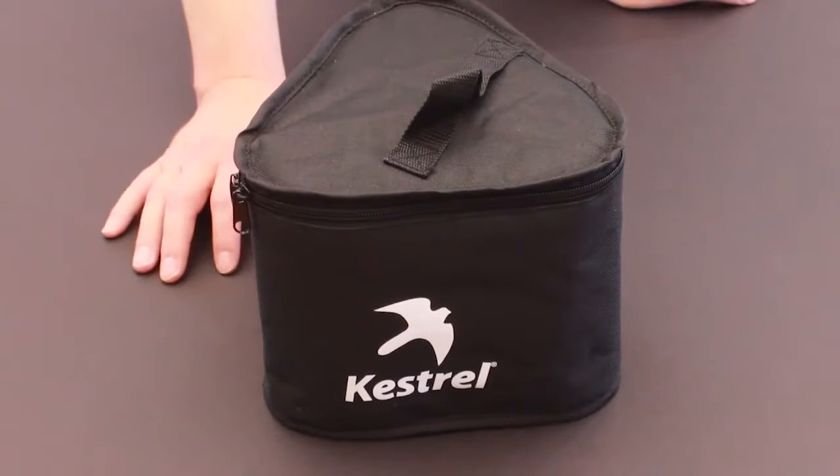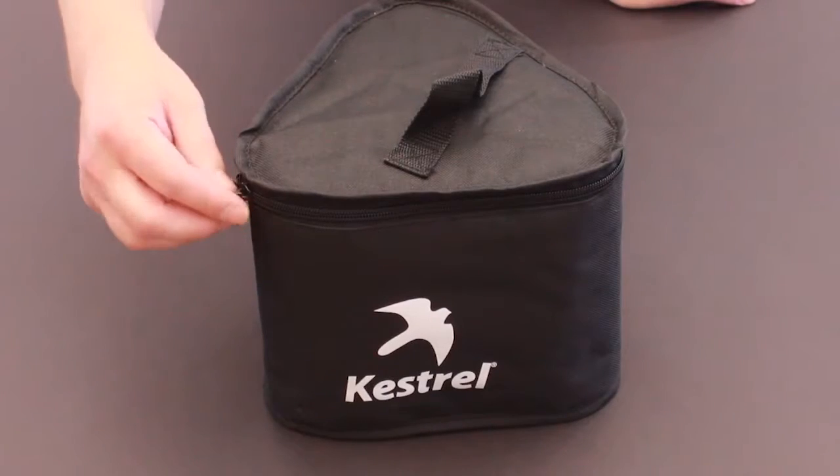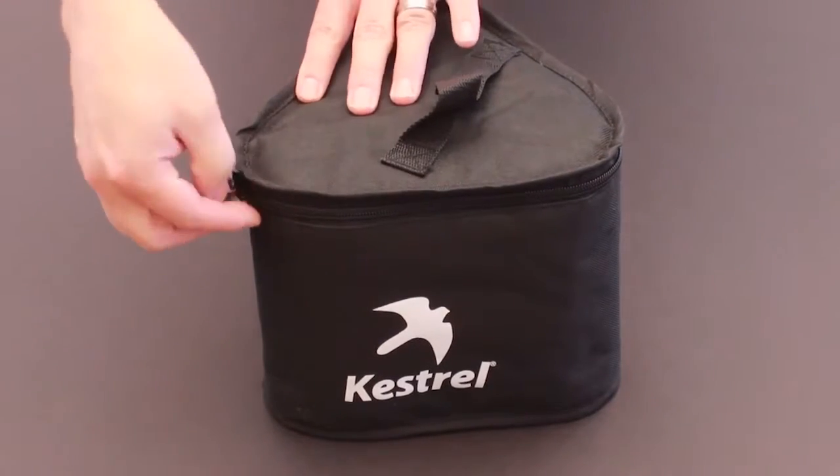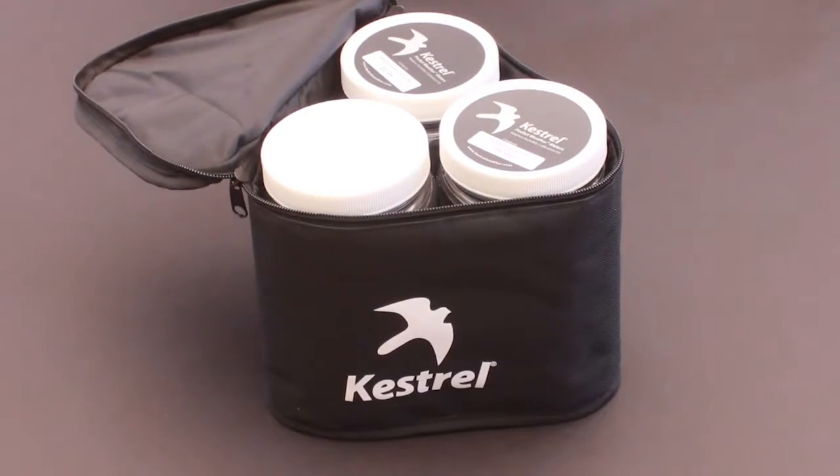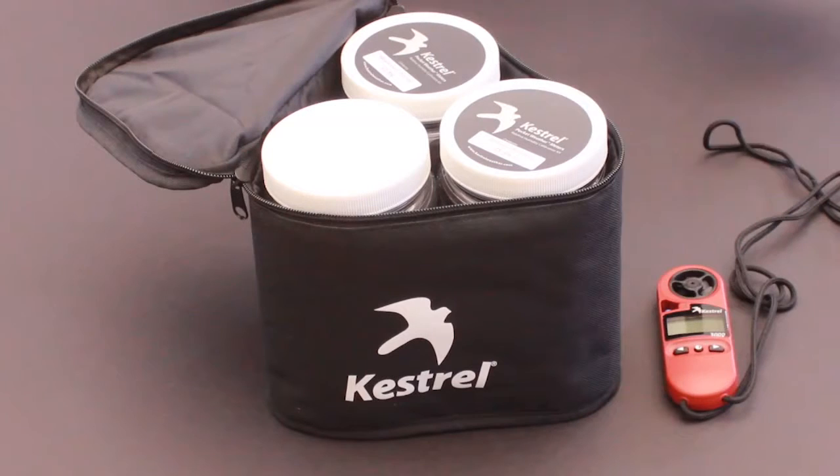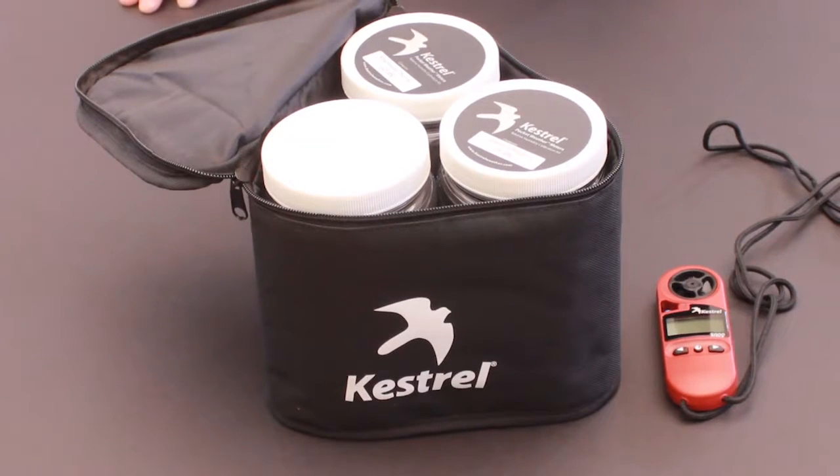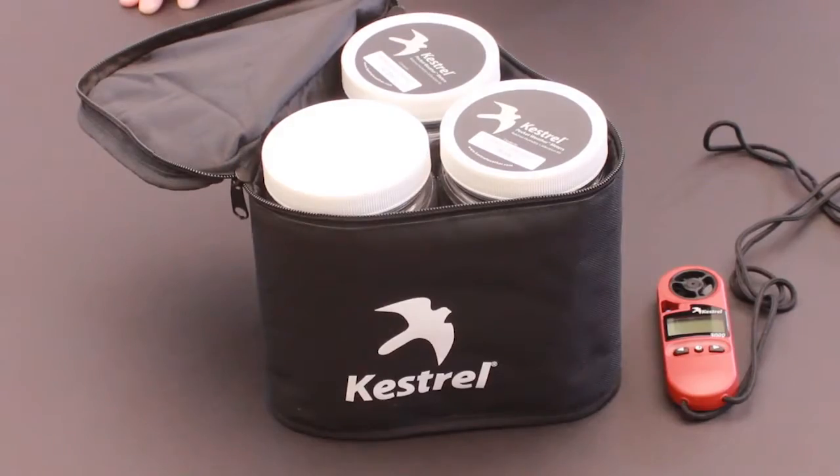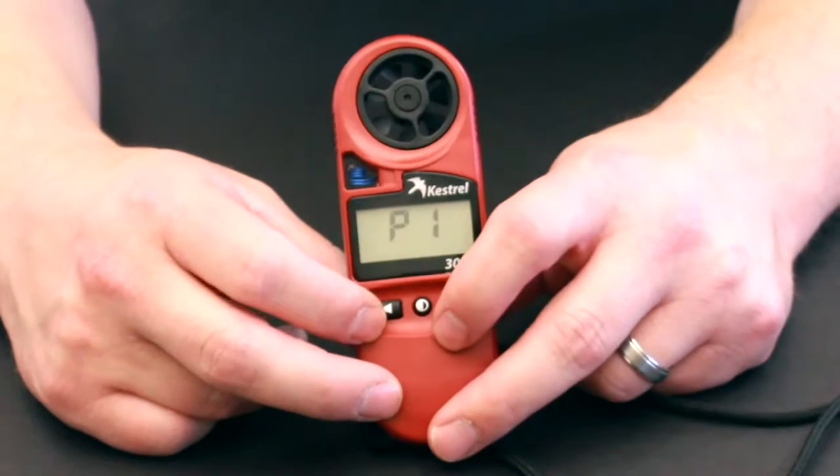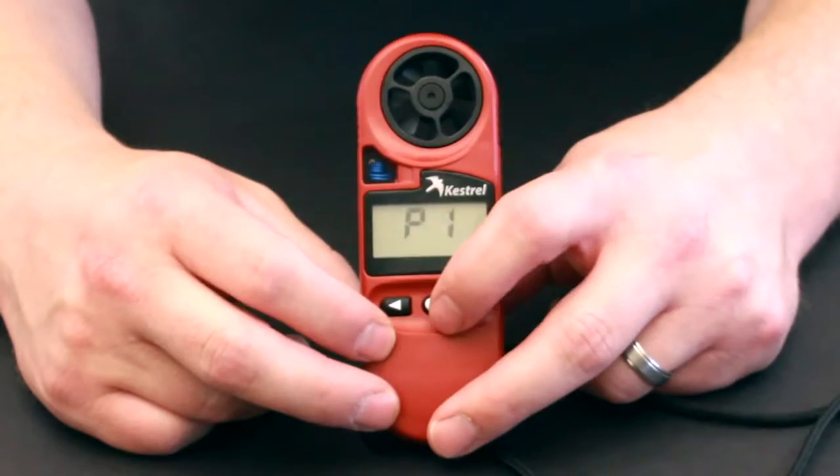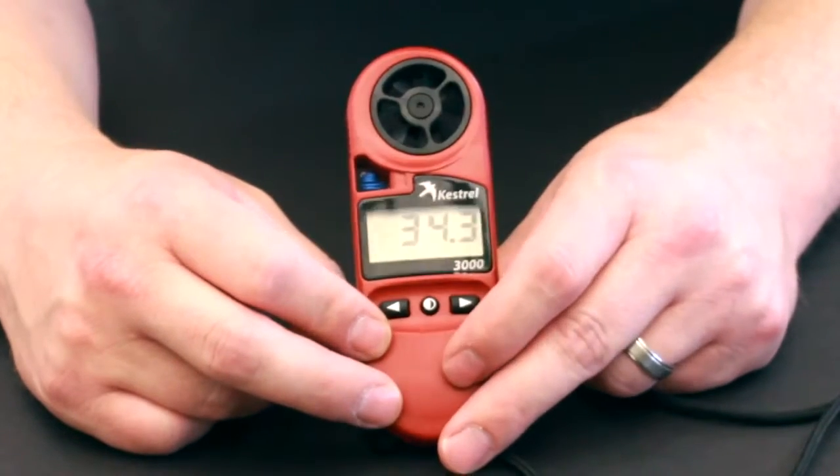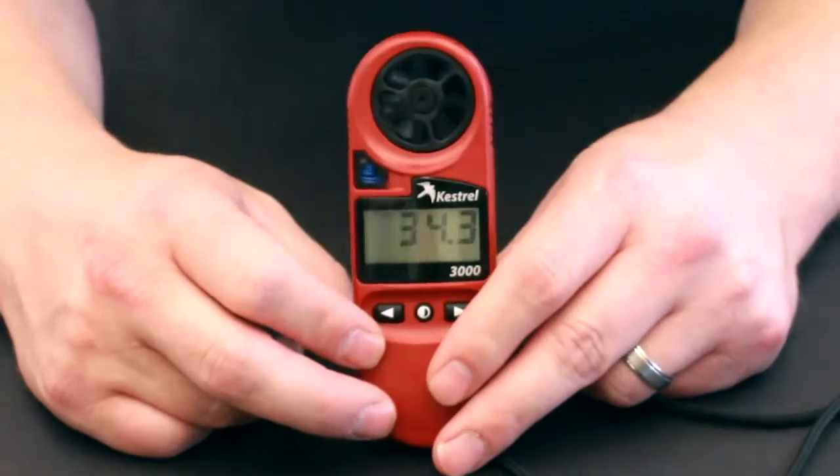After a suitable amount of time has passed, we recommend 10 hours. This will all be at the same temperature and we can start the process to do the calibration. Now open it up and we are going to start with a Kestrel 3000 series. This will work with any of the Kestrel 1, 2, 3s that have humidity in them. You will start by hitting the left button with the center button so that P1 appears.